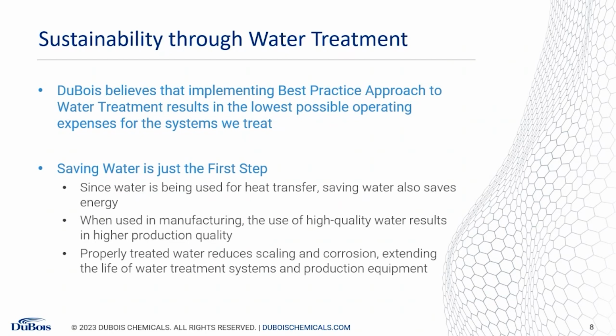And finally, if we properly treat water, we prevent it from scaling and corroding. Water is a universal solvent. It's going to eventually corrode whatever it touches. When we do water treatment, our chemistry is designed to prevent corrosion and make water less corrosive or non-corrosive, but it's also going to prevent it from scaling. So all those things, calcium, magnesium, carbonate, phosphates, everything that's dissolved in water, especially at temperature, is going to have a tendency to scale up.